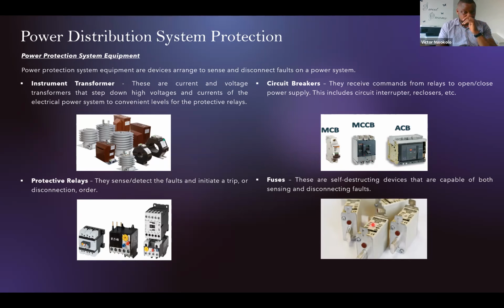It can trip in the presence of fault. So a fuse does the work of an instrument transformer, a protection relay, and a circuit breaker in a protection setting. In low voltage systems, some circuit breakers can also do the job of sensing and tripping. For instance, with the thermomagnetic property of a circuit breaker, it can sense for overcurrent as well as overload in the system. So a circuit breaker and a fuse can do the job of sensing and tripping in some systems, especially in a very low voltage system.